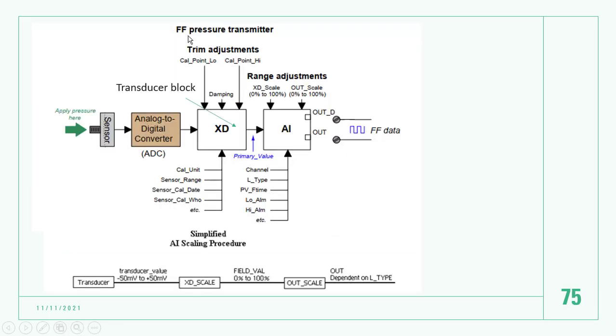This is the Foundation Fieldbus pressure transmitter. They have an AI block and a transducer block. If you do some calibration, your trim is just here: low cal point, high cal point. If you range, it is just in the AI block: transducer scale, out scale. This information is all in the transducer block and the AI block.